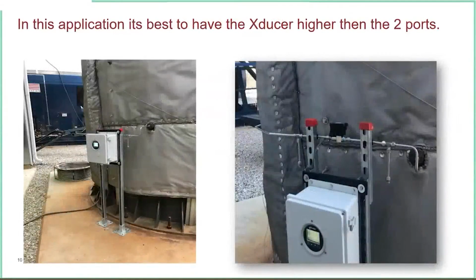And you can see here on the left hand side, we had a couple of pieces of unistrut, but they weren't tall enough in the original installation. So you can see the piping actually is going downhill to the DP transducer, and that we kind of knew from the beginning was not a good idea. It just strictly was that we didn't have long enough unistrut. So the distributor was kind enough to go ahead and add 8-inch pieces and then change the piping so that we went uphill and kept the water away from that DP transducer. And you can see they've leveled that DP transducer nicely, and that product worked well and no problems. It's been installed for 6 months, and it works well.